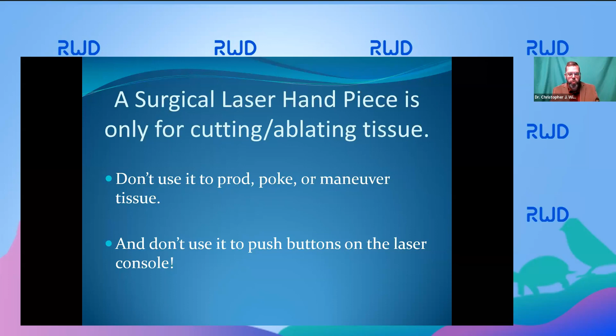Also, please don't use the handpiece to touch the buttons on the laser console. This is not something covered under your warranty, yet it remains a common cause of damage to a laser console. Instead, touch the buttons with a syringe plunger. Put one in with each of your laser handpieces and surgical packs, and if you tape a shallow cup to the side of the laser, be it CO2 or diode, you can store the plunger out of your pack right next to the control panel and still touch only the end of the plunger with your gloved hands to program while you're gloved in.